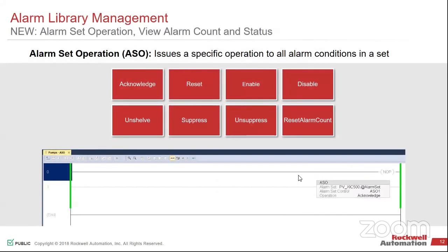Inside of the code side of it, I can now introduce logic in either my ladder code or function block to be able to manage my entire structure. So again, if I'm looking at a boiler, I can see if any alarm triggers inside of my boiler routine. So the same way that you would normally do this from an HMI setting, I can now do as part of the controller. And I can do that dynamically and make changes on anything that I want to see.